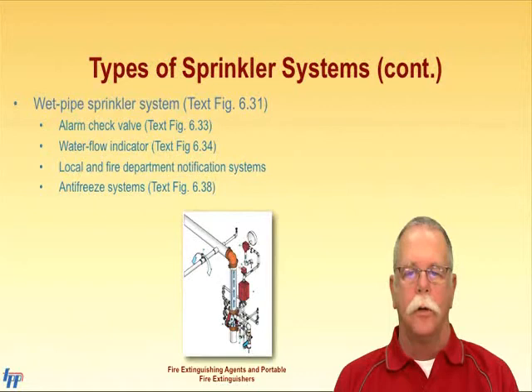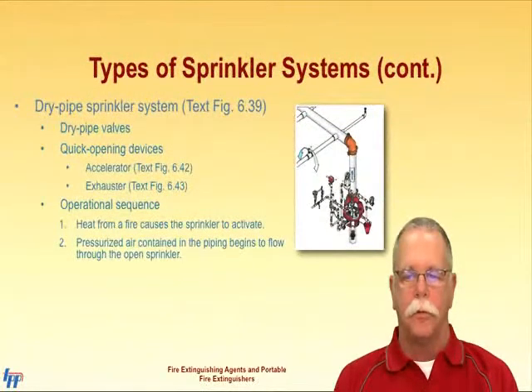The wet system is the oldest and simplest system. Water, under pressure, is in the system at all times. However, they cannot be installed in freezing areas without some type of freeze protection. The alarm check valve and water flow indicator are valves that transmit an alarm when water flows through the system. They work in slightly different fashions that are described in the book. These systems tie into a local alarm and fire department notification system, minimizing fire and water damage and improving occupant safety. Antifreeze systems are used in wet pipe sprinkler systems that are exposed to freezing conditions.